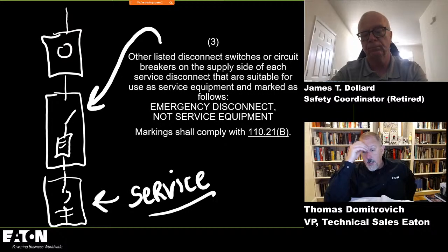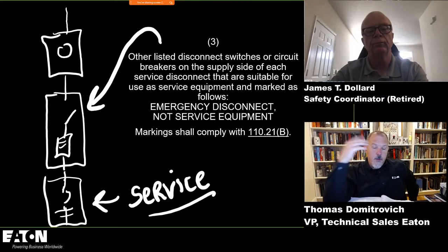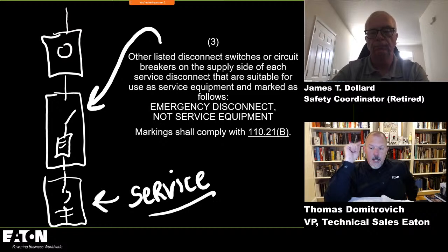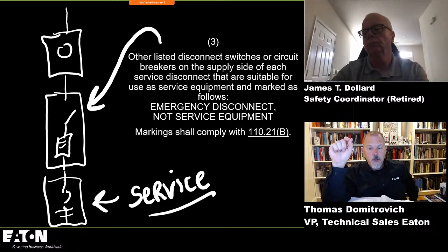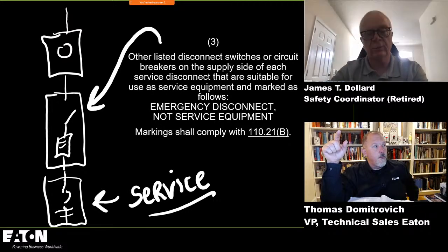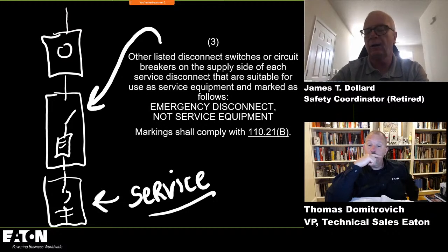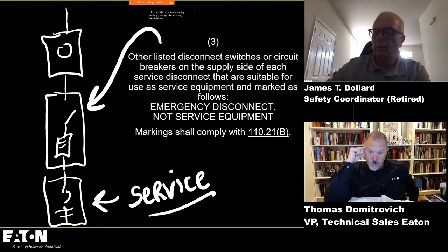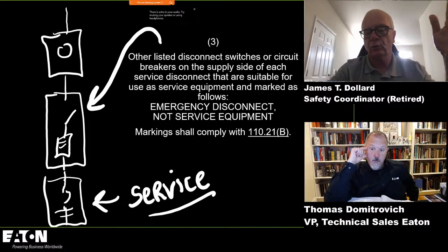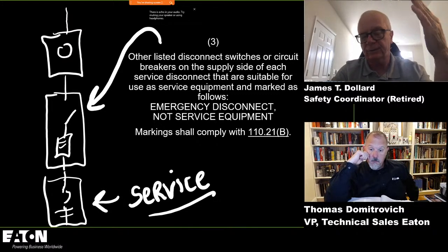Right, that's true. So Bruce says, when using the utility disconnect ahead of the meter, that's your meter disconnect. He asks, how do you get around the NEC requirement stating that service entrance conductors shall not be broken? That's not a service entrance conductor on the primary of that meter, is it? Well, it would be. In a dwelling unit, the way you have it drawn, there's going to be overhead conductors from the utility and a drop. That's a service drop. That's right. And then we've got our service point, and that's where we're going to put, for example, a service head and SE cable coming down.